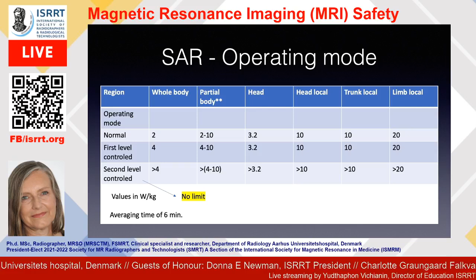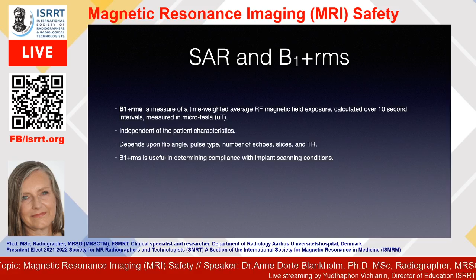So B1 plus RMS is a measure of a time-weighted average RF magnetic field exposure calculated over 10 second intervals and measured in microteslas, and independent of patient characteristics, which is actually opposite to the SAR models, where different vendors may use different SAR models. So that's one of the reasons why B1 plus RMS is used. The B1 plus RMS depends upon the flip angle, pulse type, number of echoes, slices and TR, and B1 plus RMS is useful in determining compliance with implant scanning conditions.